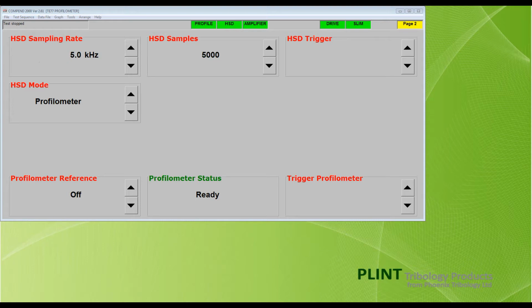While a measurement is taking place, the HSD box in the status window changes to cyan, returning to green once the profile is measured. The Profilometer status box will display measuring and will return to ready once the measurement is done. Setting Profilometer reference to on indicates to the software that the measurement taken is the reference measurement. All subsequent measurements will then be taken with the Profilometer reference set to off.